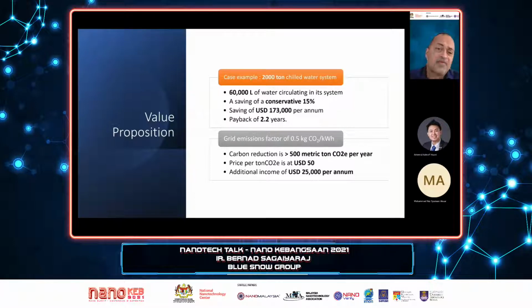So a rough calculation of 60,000 liters of water circulating in the system, we needed to change with nanofluids. Remember, the savings was about 32.7%, but for our calculation purpose we just use a conservative 15%. That alone gives you savings of 173,000 USD per annum, with a payback of 2.2 years, and that's pretty good. For most energy efficiency projects, we look at a payback within 2 to 3 years, and that's considered good.